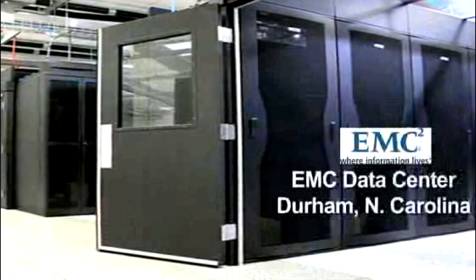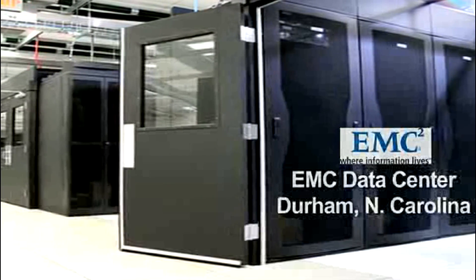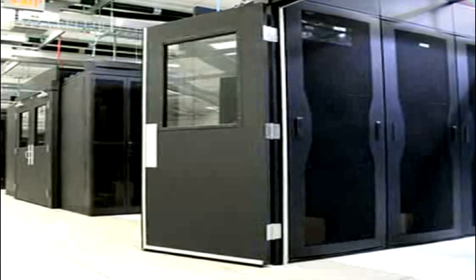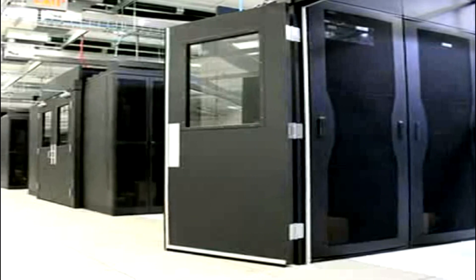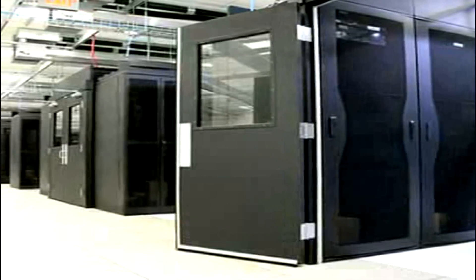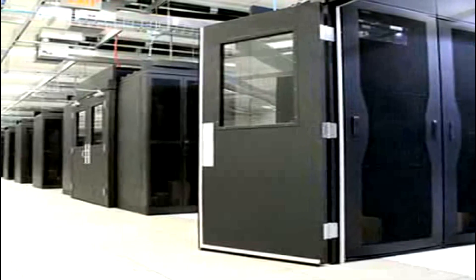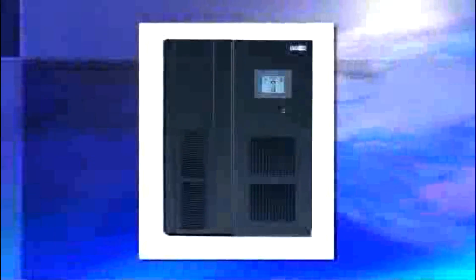The EMC Data Center in Durham is a Tier 3 system as defined by the Uptime Institute. The battery-less UPS system is a 2N redundant system A and B design. The Data Center comprises 10,000 square feet of raised floor area at 100 watts per square foot.